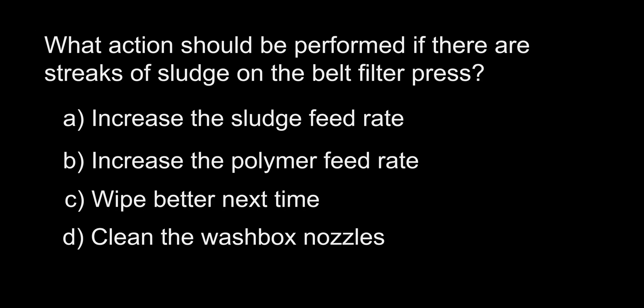What action should be performed if there are streaks of sludge on the belt filter press? A. Increase the sludge feed rate. B. Increase the polymer feed rate. C. Wipe better next time. D. Clean the wash box nozzles.